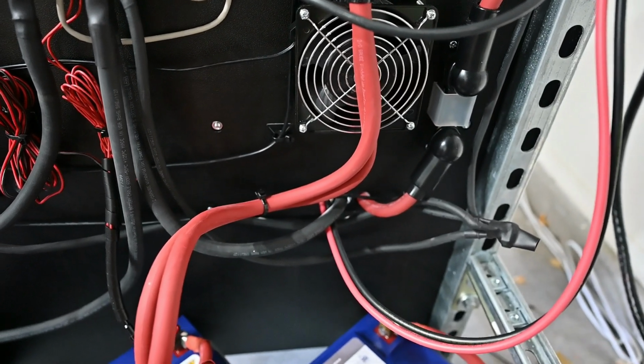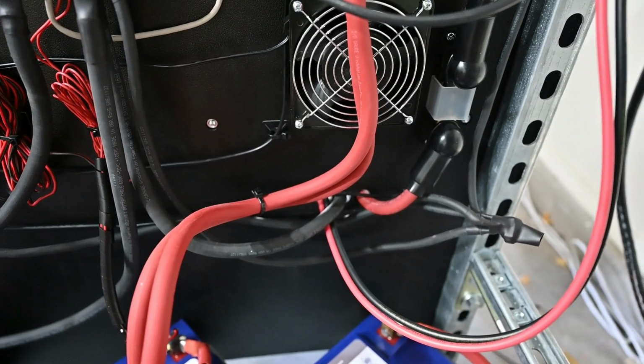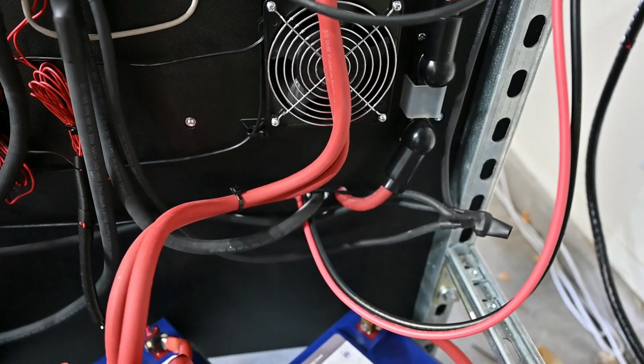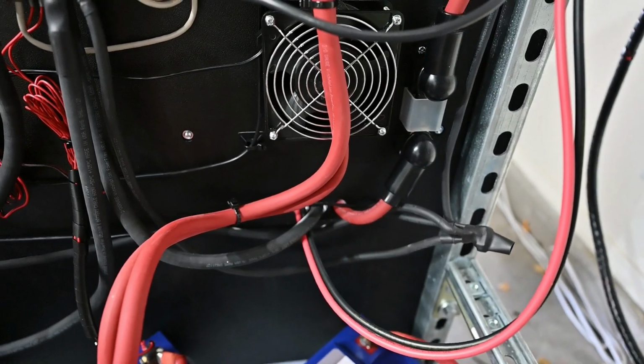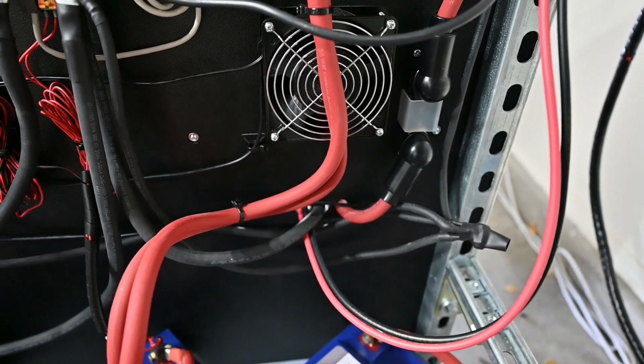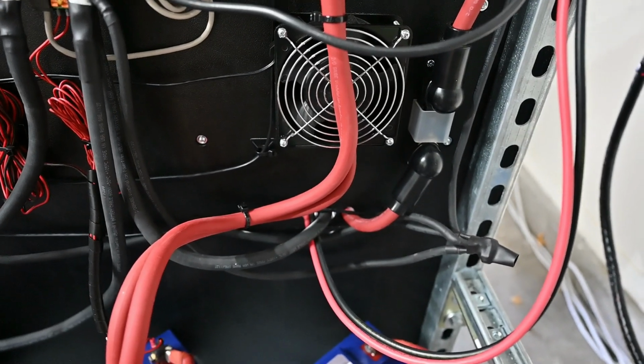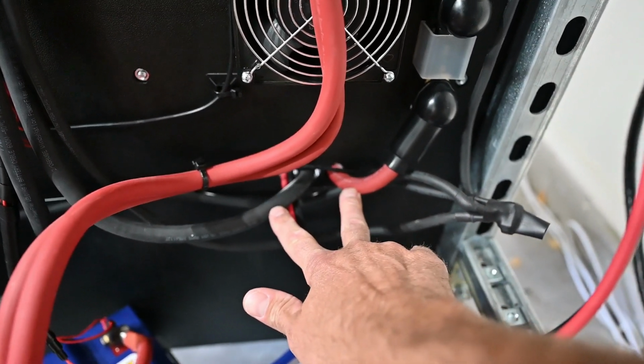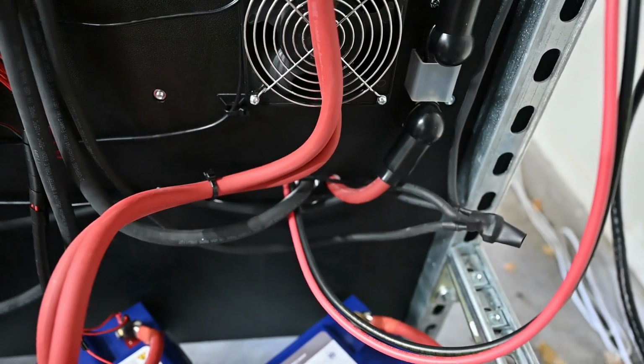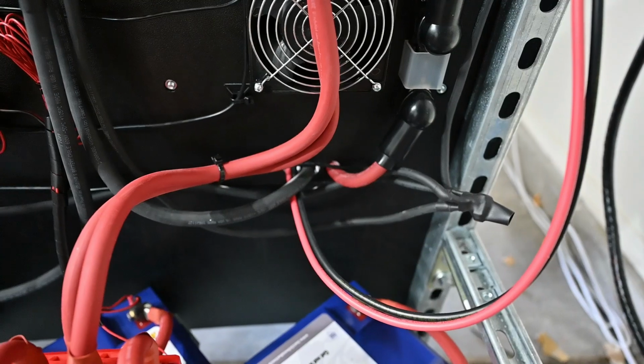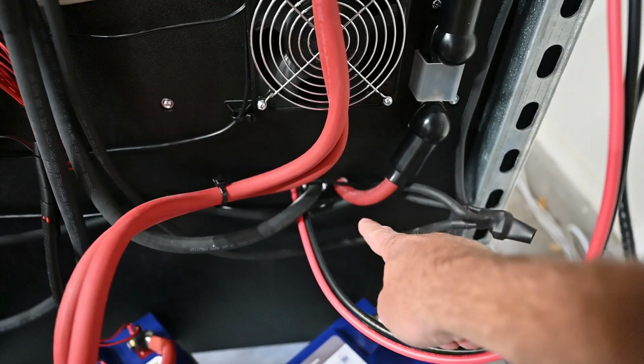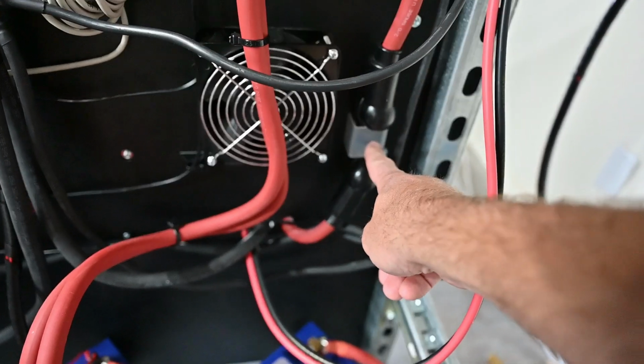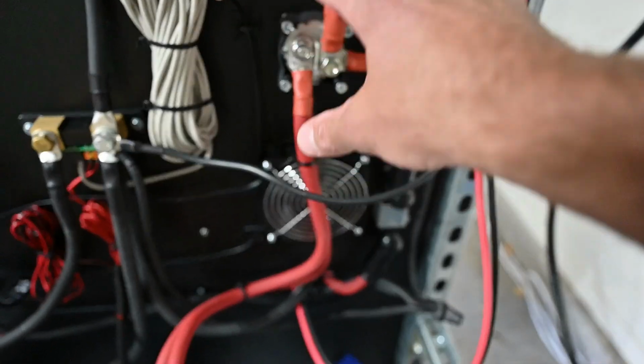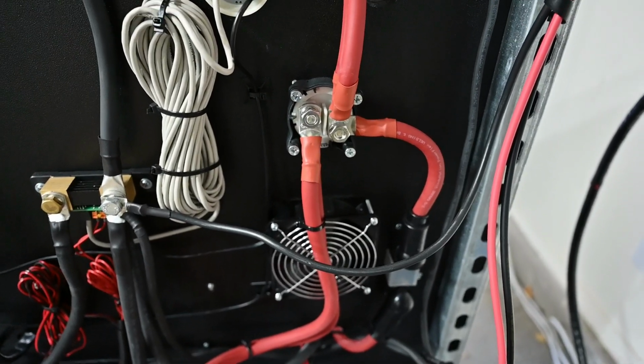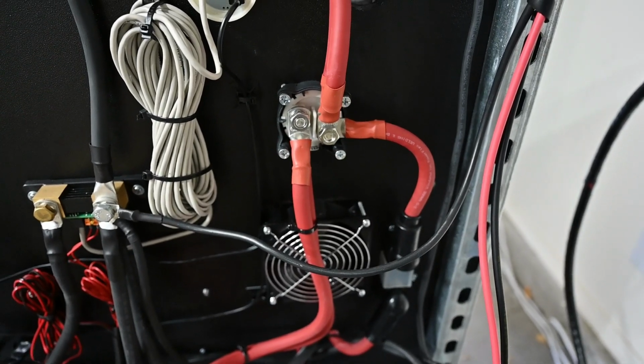And then the charge controller converts high voltage DC to low voltage DC, and also finds the maximum power point of the solar array. These two big fat cables, these are 2-aught cables, carry the current supplied by the charge controller. The positive goes through a 200 amp fuse to a main disconnect. All of this is low voltage, so it's safe to touch, but I generally don't touch it.